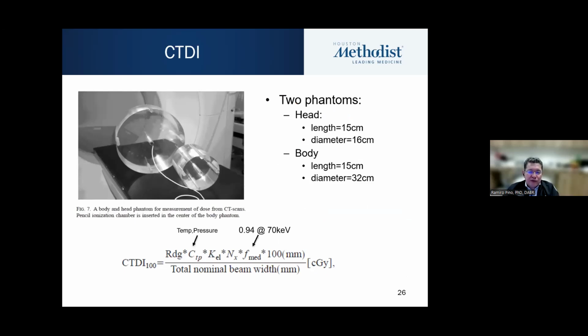Typically, 2 phantoms are used. A head one, which has a smaller diameter, 16 centimeters, and a body one, which is about 32 centimeters. And here we have the formula for CTDI 100. Obviously, we need to correct for temperature and pressure. We have a conversion factor, the reading, and the calibration factor of the detector of the pencil ion chamber.